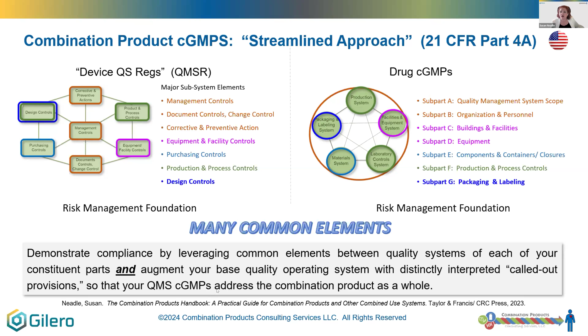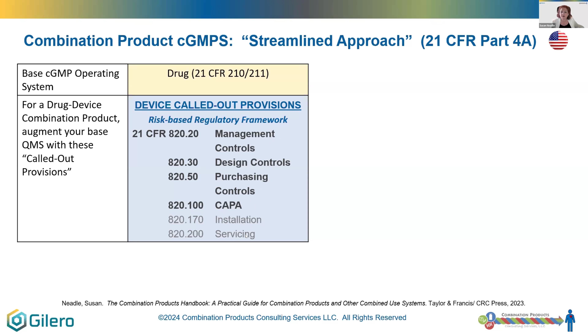Okay, and so just explaining this a little bit further, and I'm going to go through this quickly. If you have a base cGMP operating system that is based on 21 CFR 210-211, or the drug cGMPs, then for your drug device combination product that includes the device, you're going to have to augment your quality system with management controls, design controls, purchasing controls, and CAPA as interpreted specifically by the device regulations. Those regulations will overrule where there's a conflict with the drug cGMPs. Installation and servicing are also expectations. Most combination products don't have those to worry about, but those are also considered called out provisions.